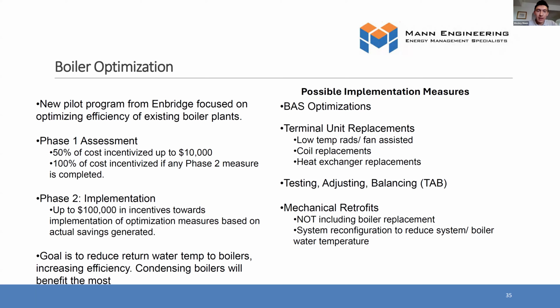So the boiler optimization pilot, this is a brand new program that's new for this year, and it's kind of on a first come first serve basis. And we are one of the approved assessment partners that you can work with on this project. So the idea behind this project is, and I've actually been talking to Enbridge for a while about having something like this, is because we notice out in the field all the time that because of the prior incentives that were primarily focused on boiler retrofits and wanting to get condensing boilers into buildings, lots of condensing boilers were retrofitted into existing systems where they're not actually getting condensing efficiency.